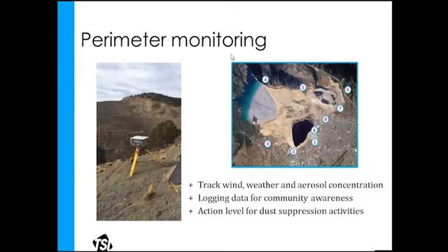Perimeter monitoring. So here's a DustTrak in an outdoor enclosure on a tripod. This customer actually has it on solar. This is a picture I took of the actual customer's setup in use outdoors. It's an open mine. The other picture I've shown is just an illustration. This is not the same customer. I just grabbed this off the internet. It's a freebie from Google. I don't know where this even is.